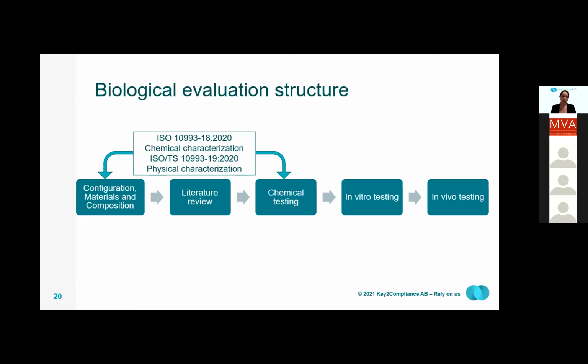Then as a next step, I call it literature review. This is where you look at the history of clinical use, or if you have, for example, existing biological safety data from a previous device or from the device under MDD. And after these two steps, you can actually come to the conclusion that you don't need to perform any testing. But if there are gaps, then you need to do testing on the device.